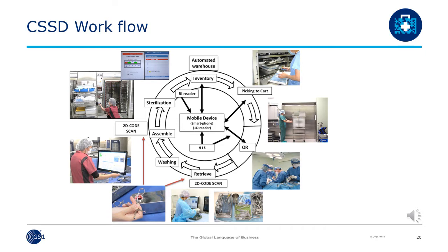Step 2. Receipt of contaminated items by the Sterile Services Department, SSD. The department receives items for reprocessing in the designated dirty zone of the decontamination area. Step 3. Reprocessing. The items are placed in the appropriate container for decontamination. The items are then washed by the washer disinfector, which also dries the items following the disinfection stage of the automated process. Once the cycle is complete, the machine transfers the cleaned and disinfected medical devices into the clean zone.